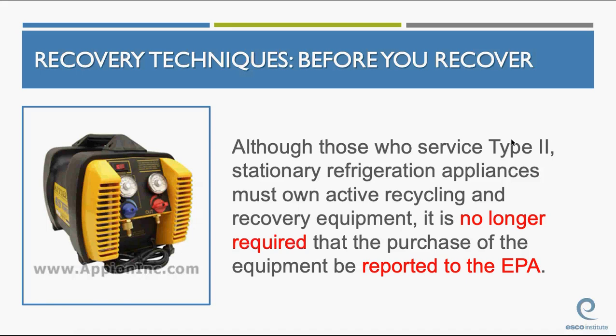Although people who service Type 2 stationary refrigeration appliances must own active recycling and recovery equipment, it is no longer required that the purchase of such equipment is reported to the EPA. This is a change from people who had studied for the prior test version. You do not anymore have to report the purchase to the EPA. You still have to own active recycling or recovery equipment. In other words, you can't use passive recovery devices on Type 2 appliances.